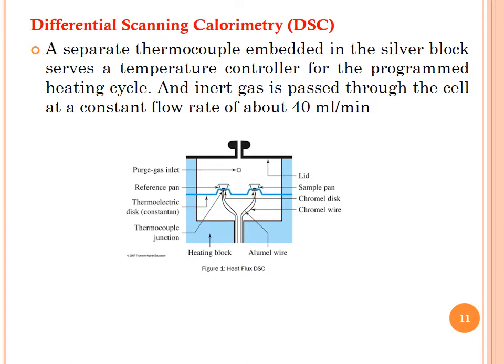Alumel wires attached to the chromel disk provide the chromel-alumel junction for independently measuring sample and reference temperature. A separate thermocouple embedded in the silver block serves as the temperature controller for the programmed heating cycle. An inert purge gas is passed through the cell at a constant flow rate of about 40 mL per minute. The purge gas depends upon the nature of the sample — it may be nitrogen, carbon dioxide, or argon.